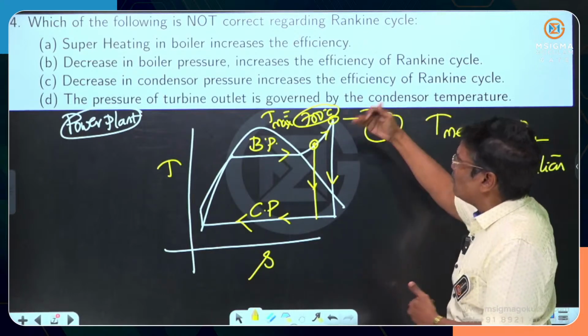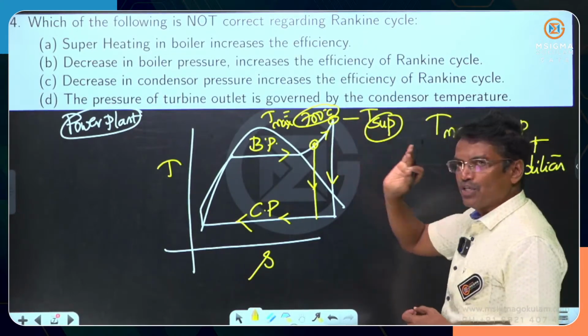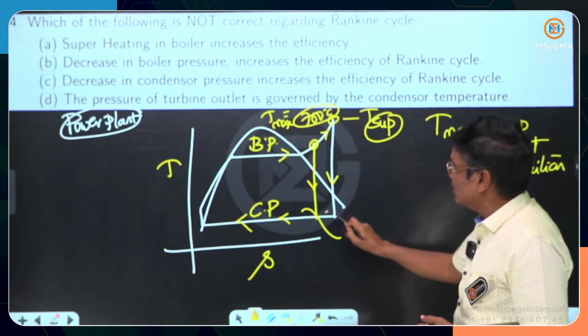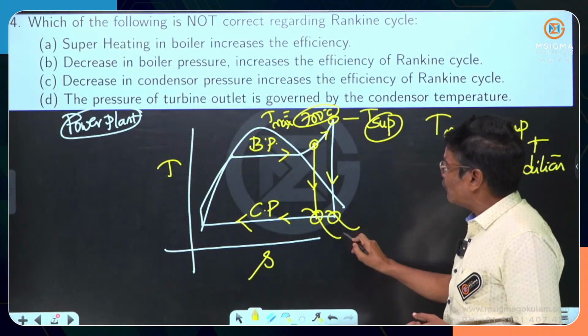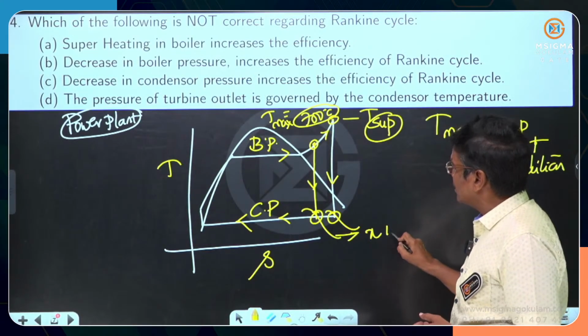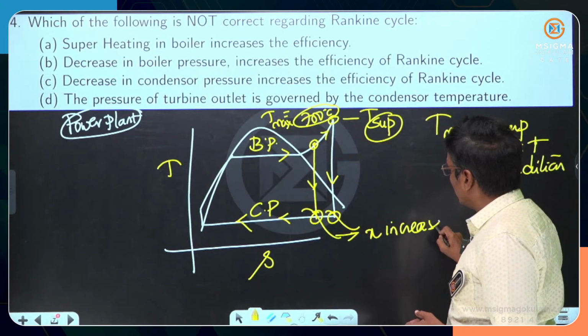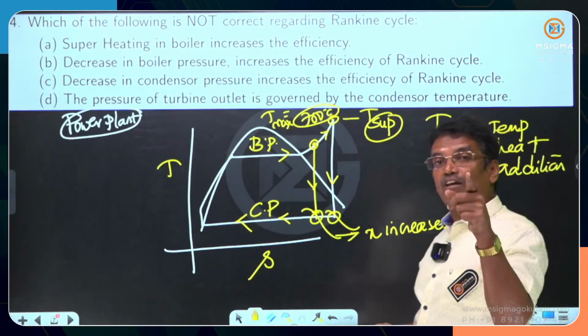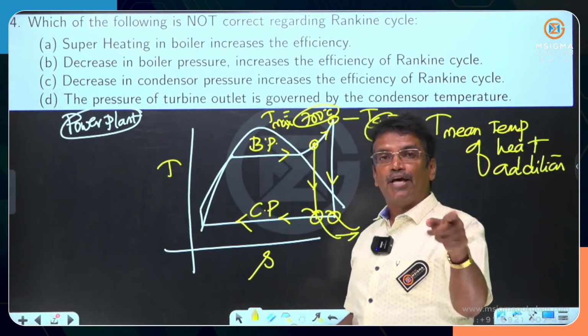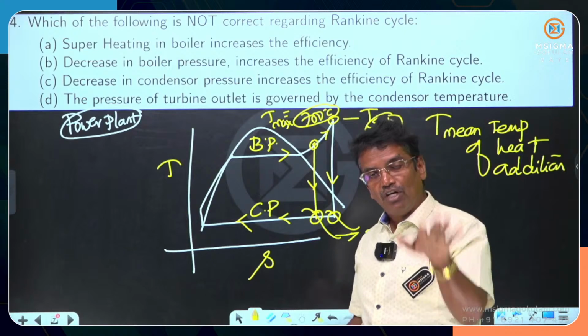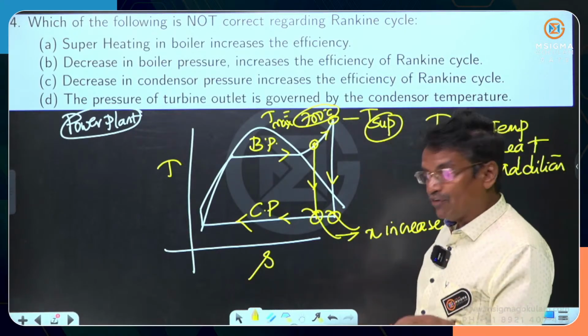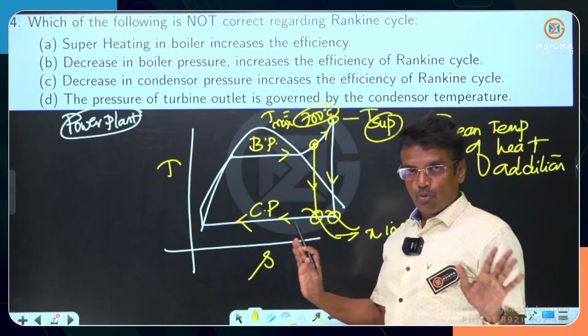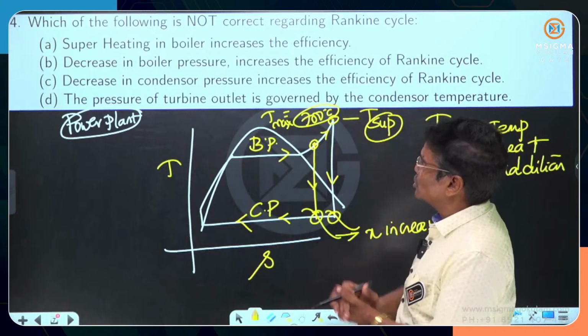But if you provide more and more temperature, definitely your efficiency will be more, and you get an additional benefit. You get an additional advantage. Your dryness fraction also will increase. X increases, thereby the quality of the steam is increasing, thereby there will be lesser turbine blade erosion. Turbine blade erosion chances will decrease. So that is the additional benefit you get. Blades are safe. They are not subjected to any blade erosion. So the first question is answered.